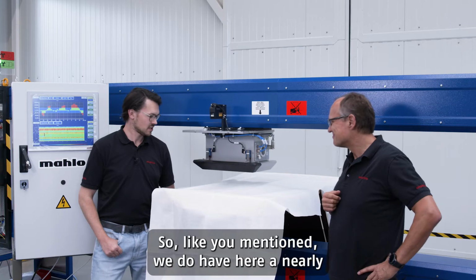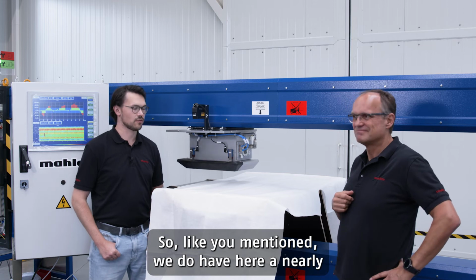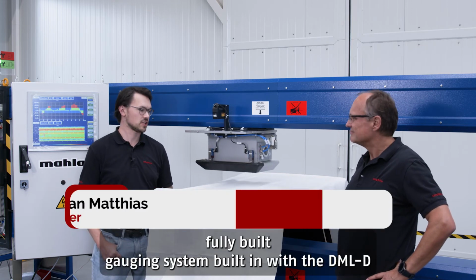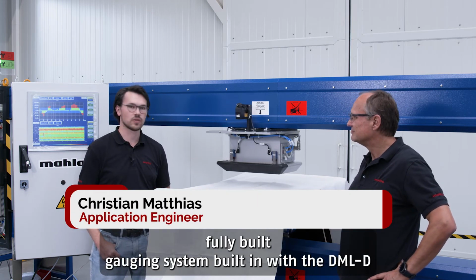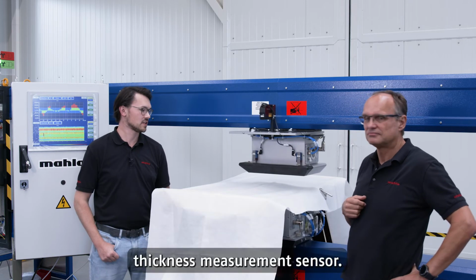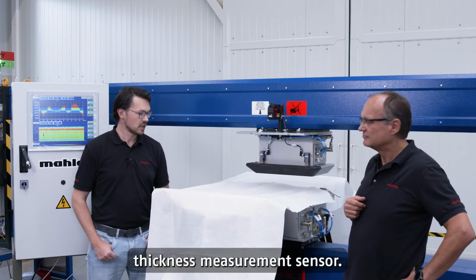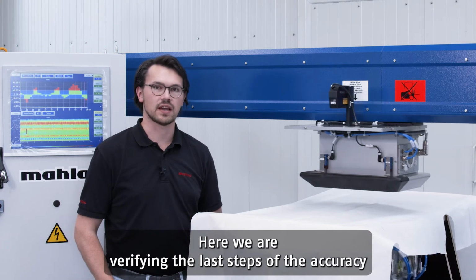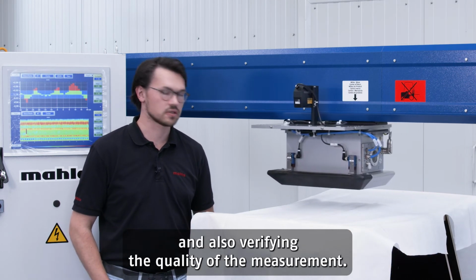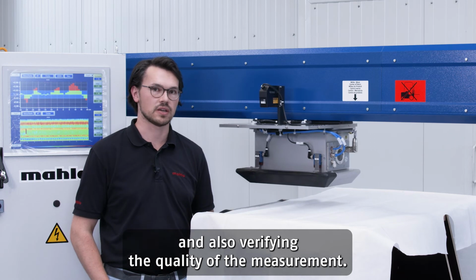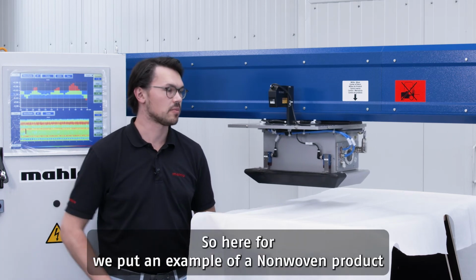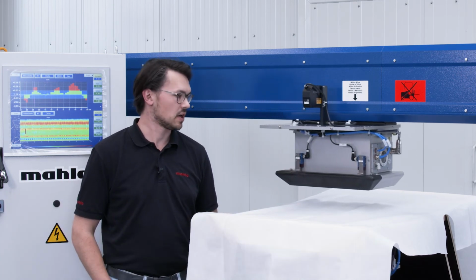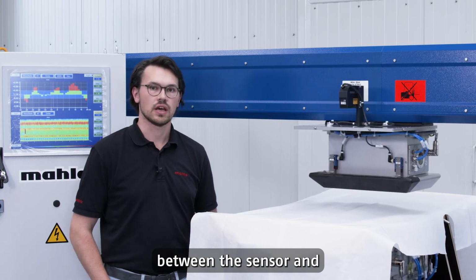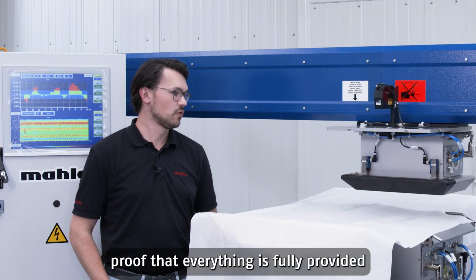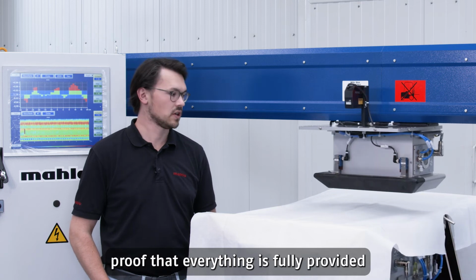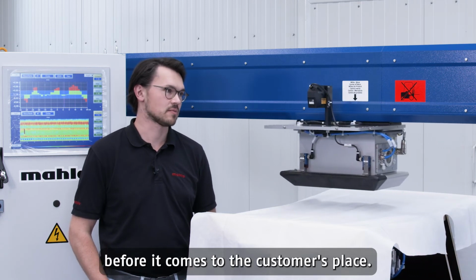Christian. So, like you mentioned, we do have here a nearly fully built gauging system, built in with the DMLD thickness measurement sensor. Here we are verifying the last steps of the accuracy and also verifying the quality of the measurement. So therefore we put an example of a non-woven product between the sensors and prove that everything is fully provided before it comes to the customer's place.